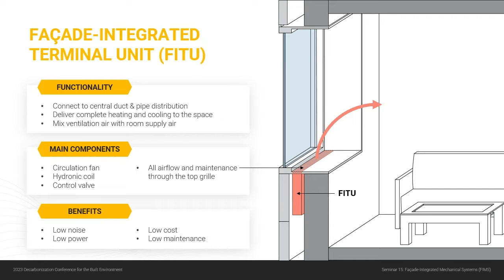Now, the last critical piece of making this system work is the Facade-Integrated Terminal Unit, or the FITU, we'll call it. So you can see it there between the old and new facade. So it's a terminal unit that fits within that narrow space, and it connects to that central ductwork and central piping to deliver the heating and cooling into the space. And it's also mixing in the ventilation air along with the air that it's recirculating within the room.